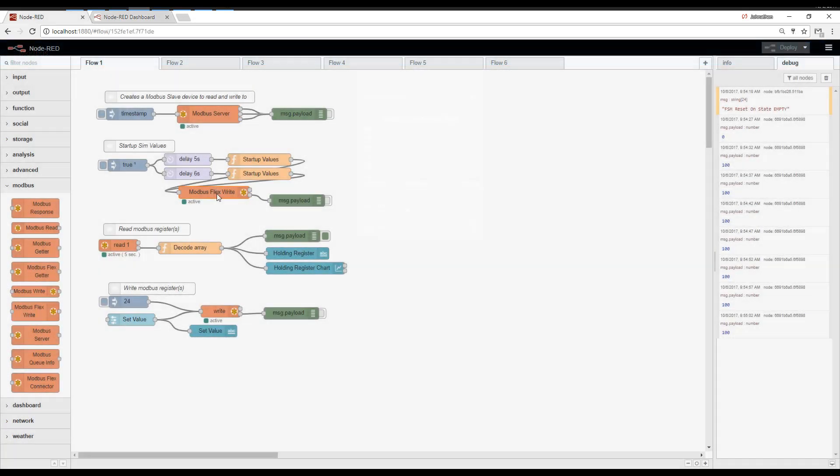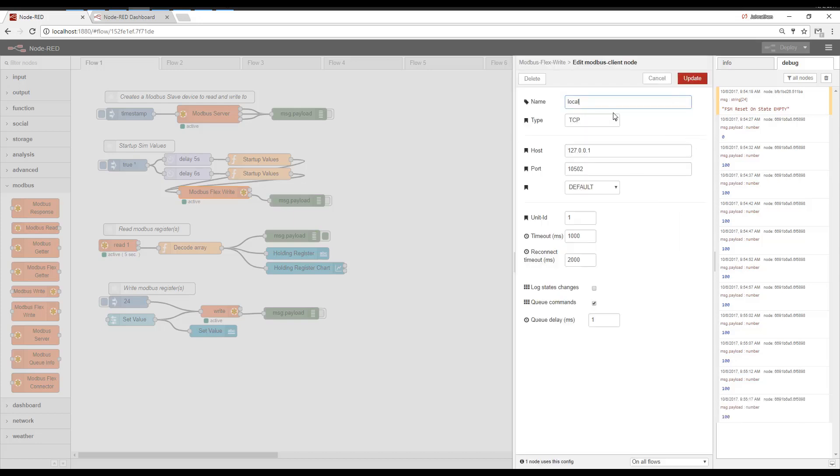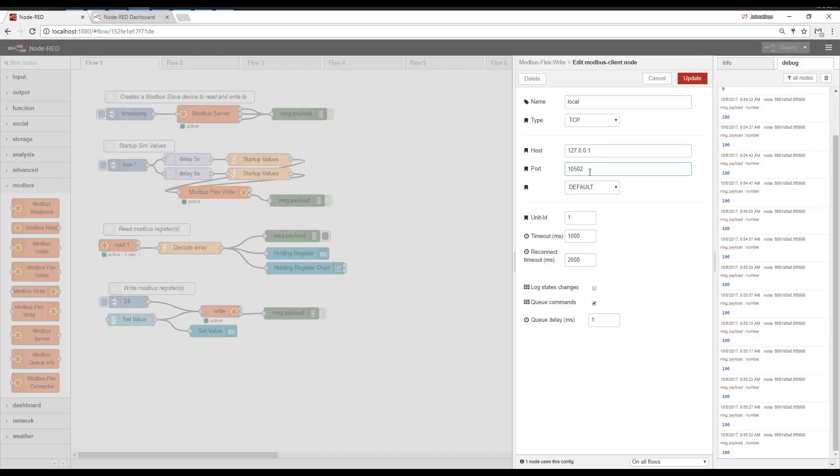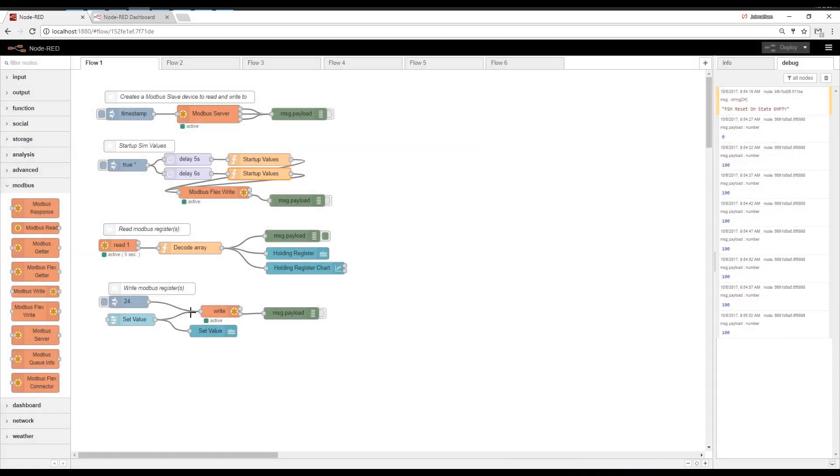One more thing to note. You can connect to many different Modbus devices. And when you set up a server, pretty much you just need to set up the type. So is it Modbus TCP, Modbus Serial? What is the IP address of this Modbus slave device we're going to connect to? What is the port? And that kind of gets you started with Modbus.